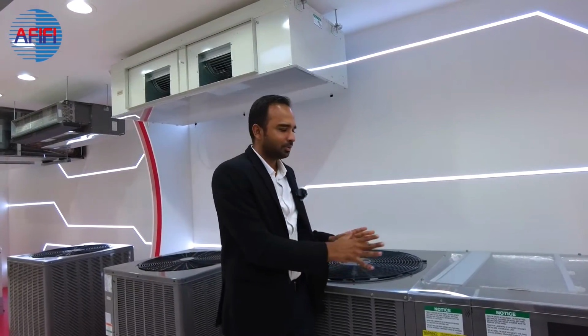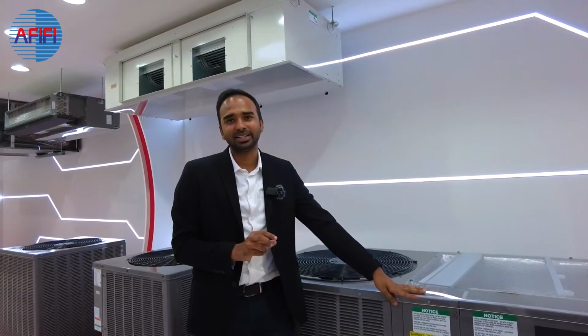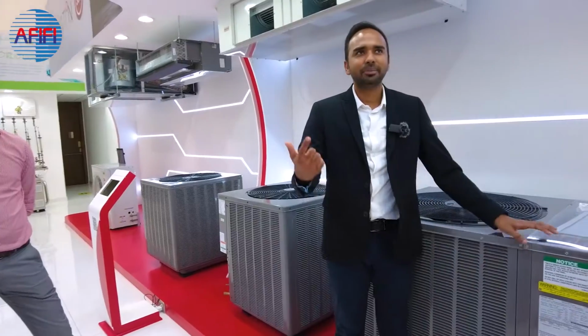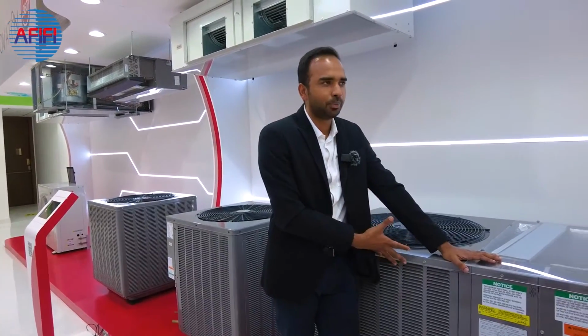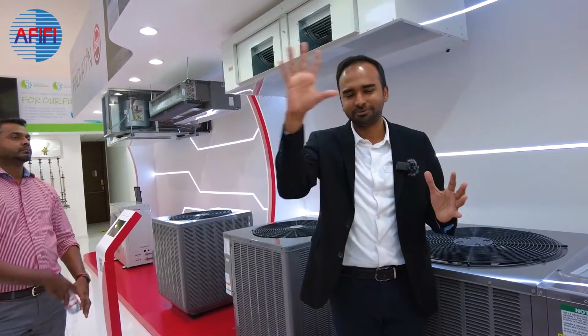For the bigger units, because they are more sophisticated, you've got dual circuits, more safety switches, and PCB assemblies. But up to 10 ton, we strictly follow relay logic systems. The old school, same as old Caprice and old Toyota. That's exactly right. Before we had the R410 series, in the R22 series, the 10 ton was divided into 2 compressors, 2.5 ton and 2.5 ton, and then you had 2 fans, dual circuit, everything. The problem with that is your overall efficiency drops a little, because you've got 2 different components, 2 different circuits, and a lot more pressure drop. With one circuit, it's a far simpler system.